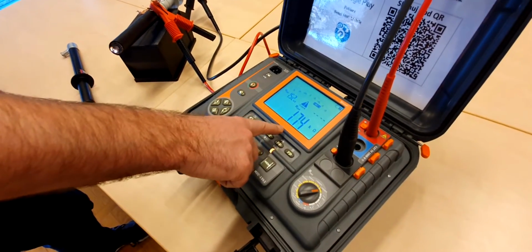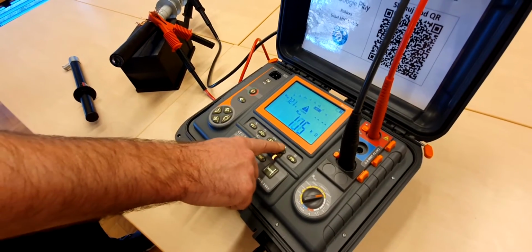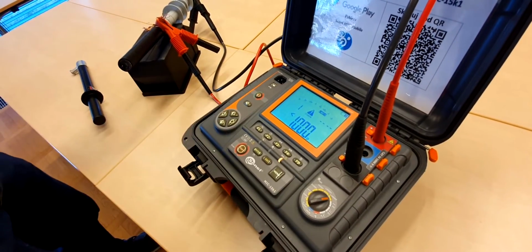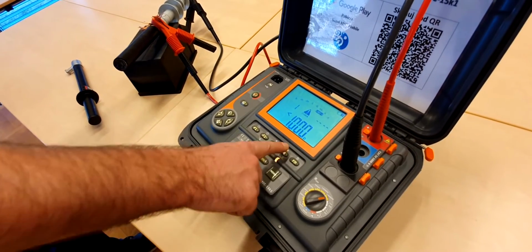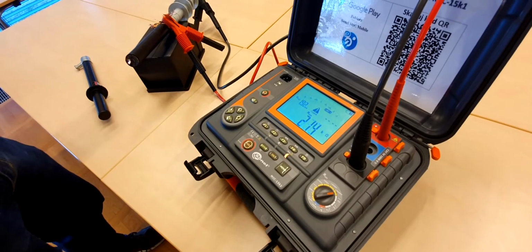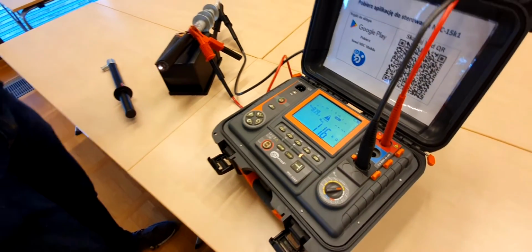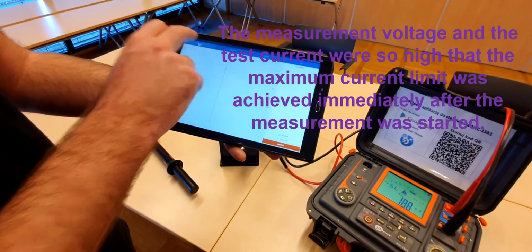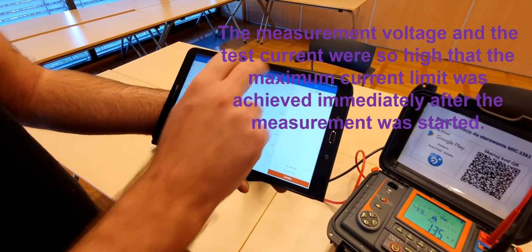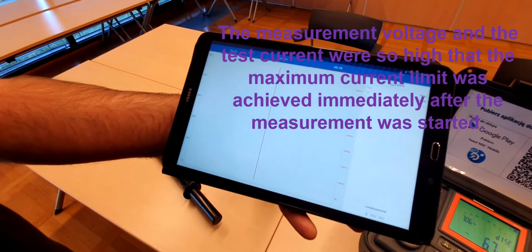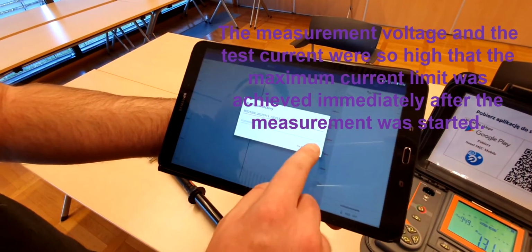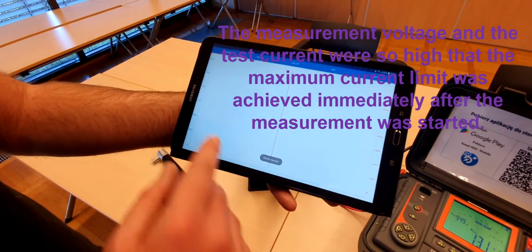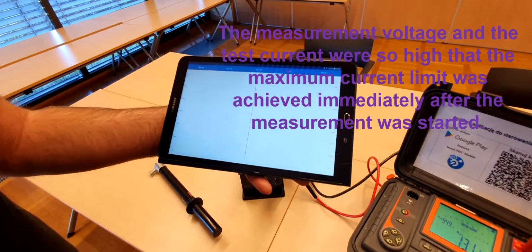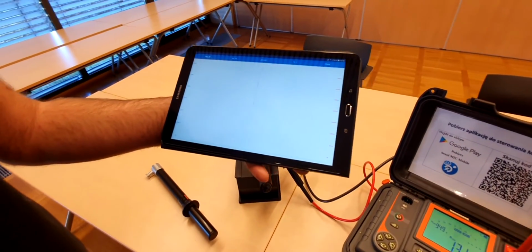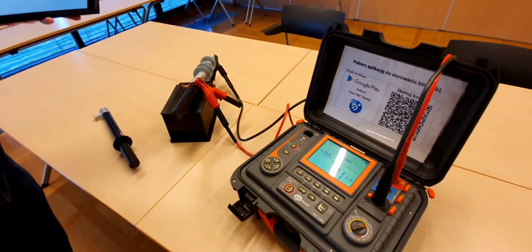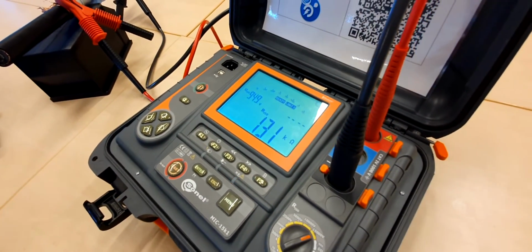We have a very low value of the resistance of insulation, although the partial discharge indicator does not indicate any partial discharges. Well, there simply aren't any discharges. Also, once we look at the graphs, we can see that the value of resistance is close to zero. So this is what the meter will show us when we have a short in the cable.